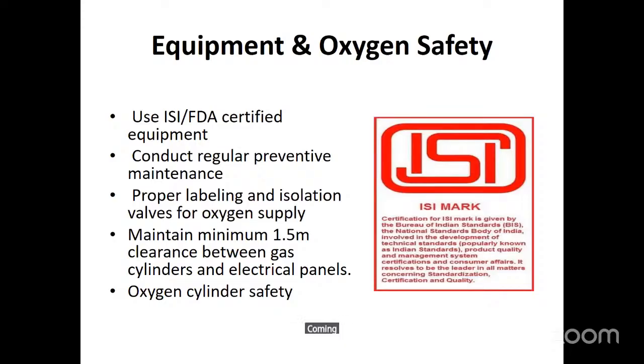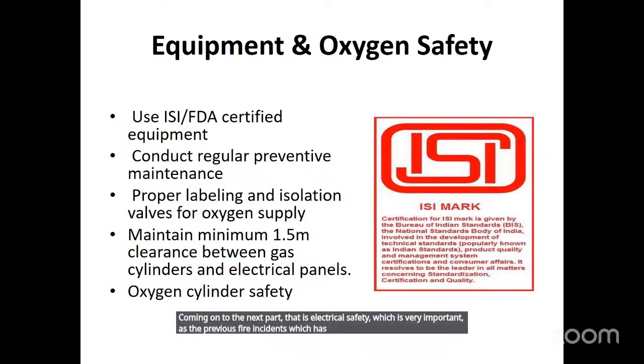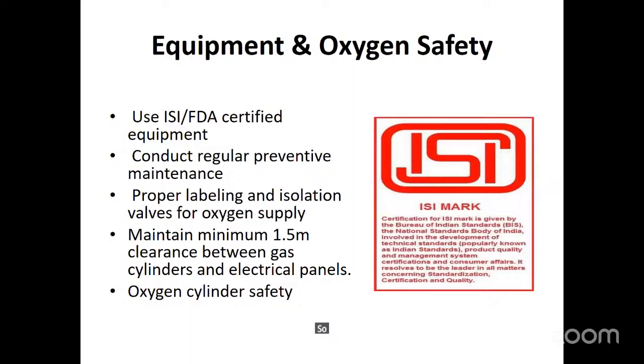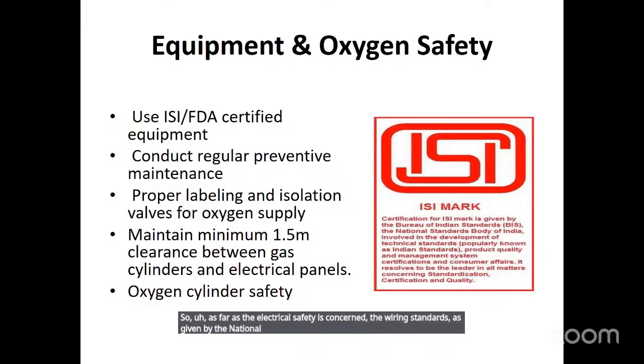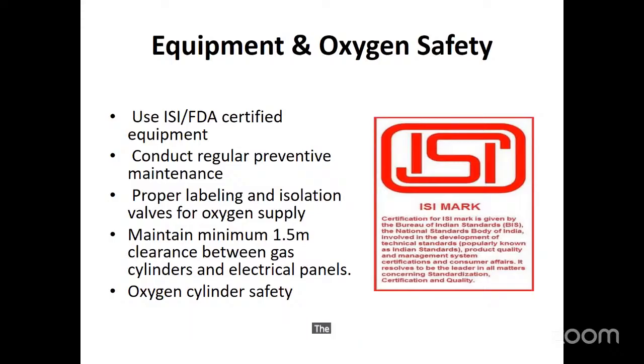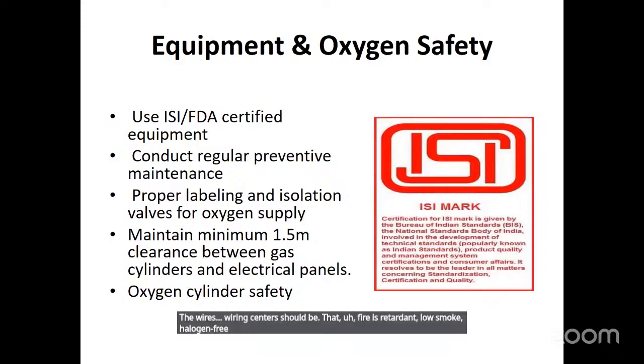Coming on to the next part, that is electrical safety, which is very important, as the previous fire incidents which have occurred are mostly caused due to electrical overload. So as far as electrical safety is concerned, the wiring standards as given by the National Building Code and also the Ministry of Health and Family Welfare say that fire retardant, low smoke, halogen free copper wiring should be used. That should be ISI standard.